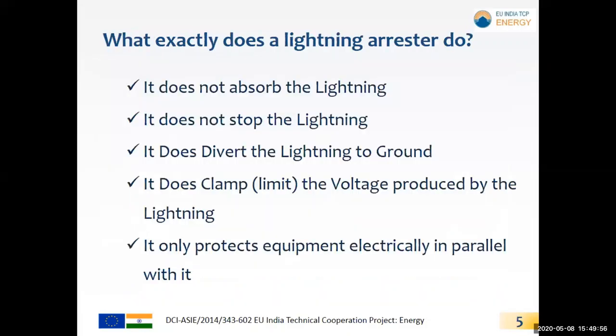First, the lightning arrestor. Is it required for a smaller system like 1 kilowatt or 10 kilowatt? A lot of people have this question, and the answer is yes, it is required. Lightning does not have a sense of where to strike or where not to—it's basically negative charge, or a bunch of electrons, and it is always attracted by positive charge. So if your system capacity is 1 kilowatt but the surrounding atmosphere has a positive charge, lightning may still hit your system.